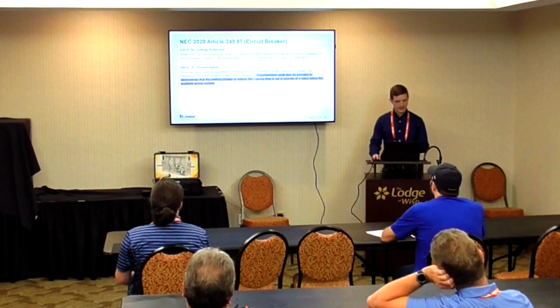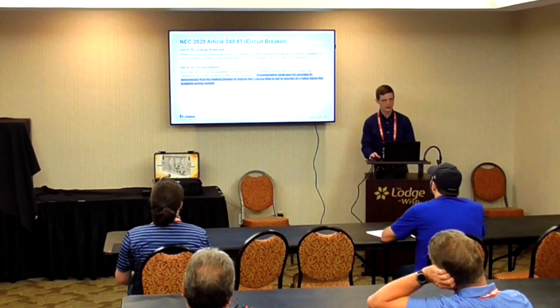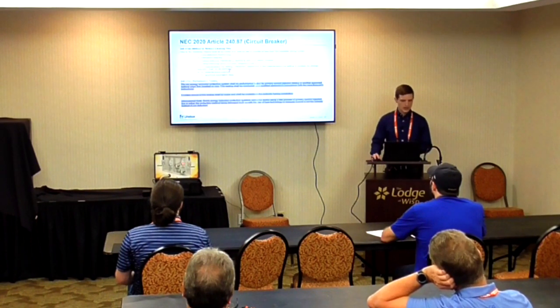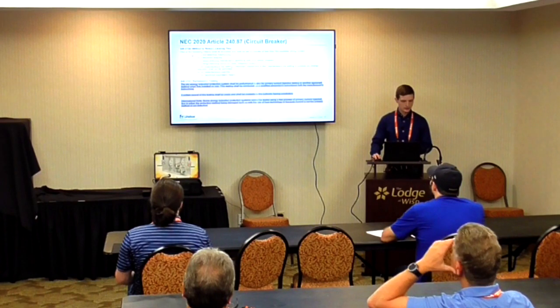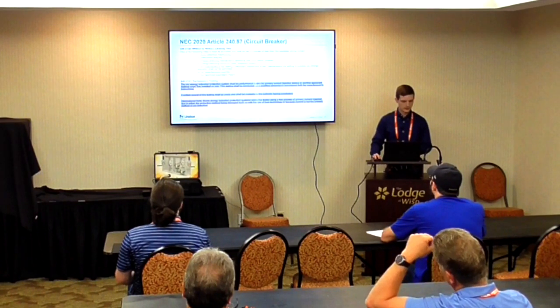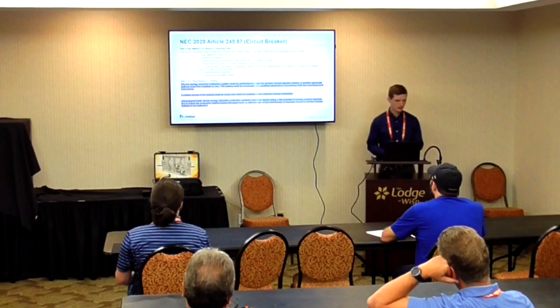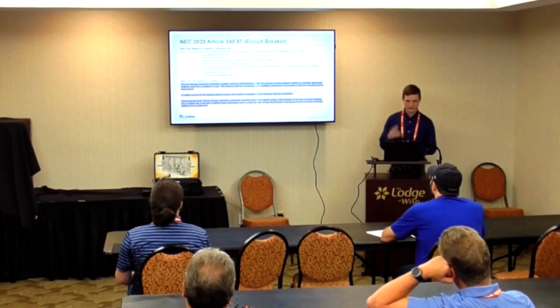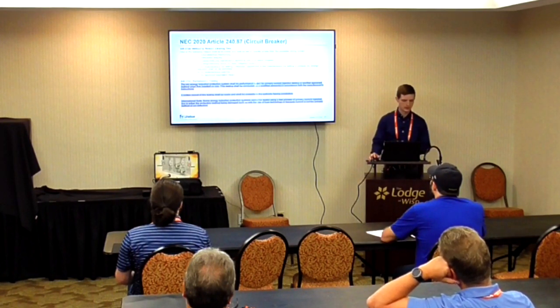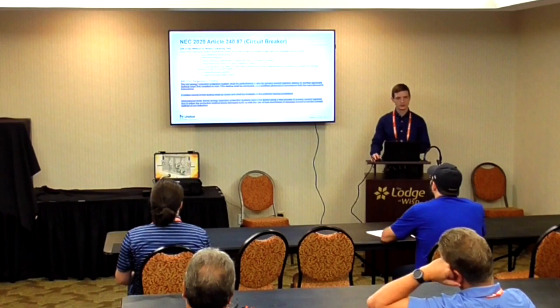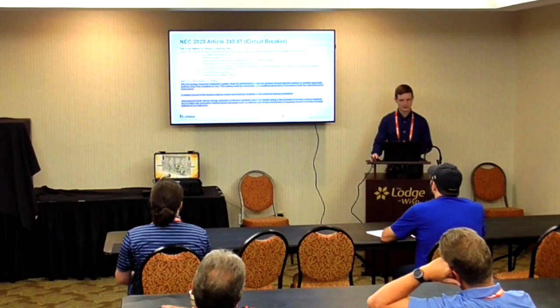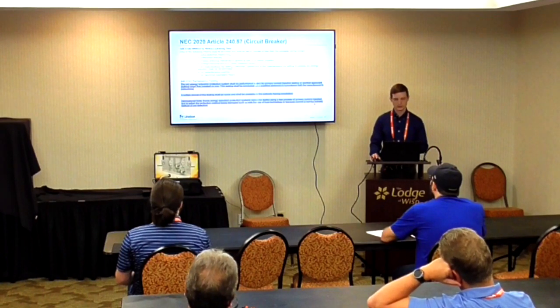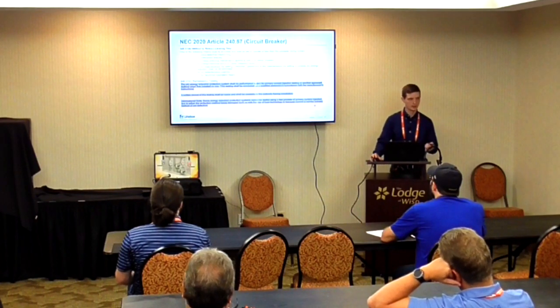is you're going to need to provide documentation that shows that this method is going to clear it within the specified time. And it's also going to mean that you're going to need to use one of these 7 methods that I referred to earlier from the NEC. ZSI, differential relays, or bus differential relays, energy maintenance, things like that. And I'll cover some of these in just a little bit. But you also need to do some performance testing. That's typically done by a manufacturer, or you can look at software like SKM, EasyPower, ETAP, things like that.